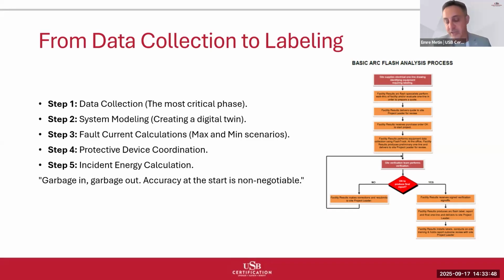Step 3, fault current calculations. We calculate available fault current at every significant location, considering both maximum and minimum fault scenarios. Why both? Because different fault current levels can affect arc duration and protective device operation, which directly impacts incident energy. Step 4, protective device coordination. This step determines how quickly the protective devices will operate to clear a fault. Faster clearing times mean shorter arc duration and lower incident energy. This is where we see the interaction between arc flash hazard levels and electrical system design, especially if the electrical system is inside a generator or rotating motor, this could be dangerous when the arc flash occurs.